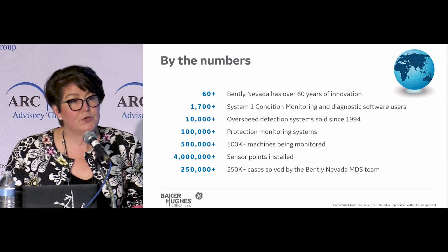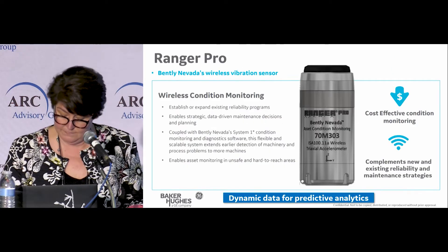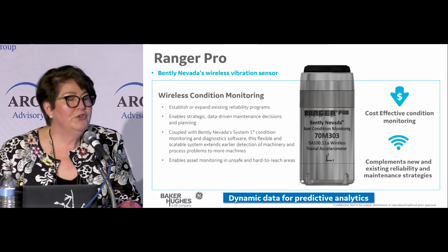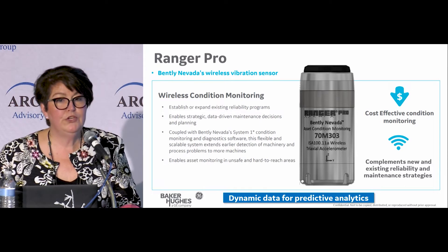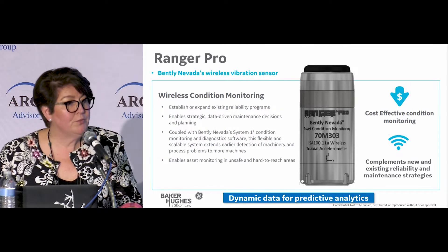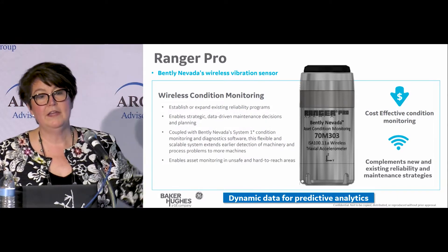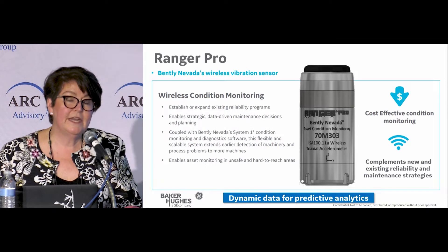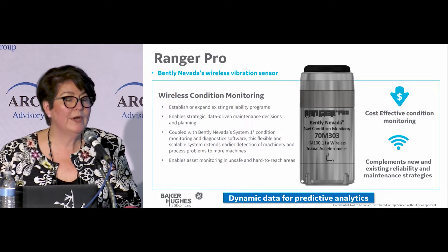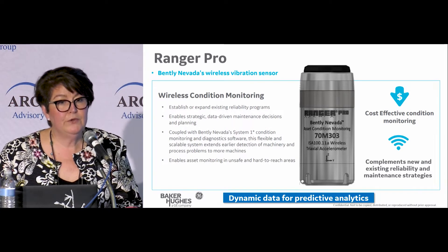Our Ranger Pro is on about 2,000 machines since our launch in 2018. When you're going to monitor a machine's health, vibration is one of the most critical parameters for diagnosing problems and determining machinery health. Ranger Pro is a vibration sensor — triaxial — so you're actually measuring the X, Y, and Z directions. It's not just gathering static data but is a dynamic sensor, taking more than 1,000 points of information per second. So it's not just a check engine light, but a tool that can be used for diagnostics.